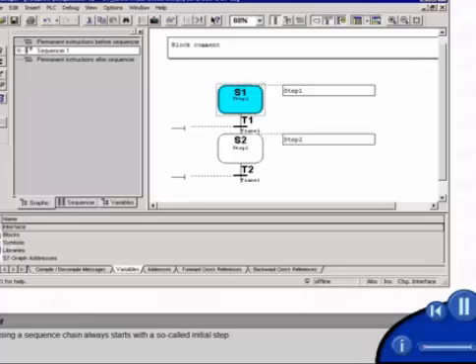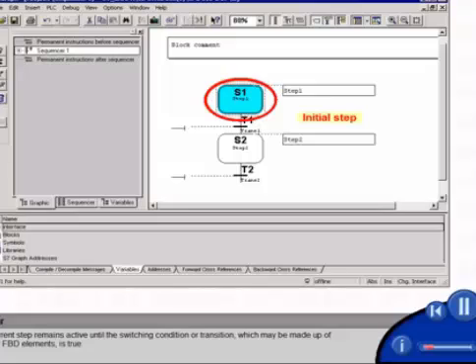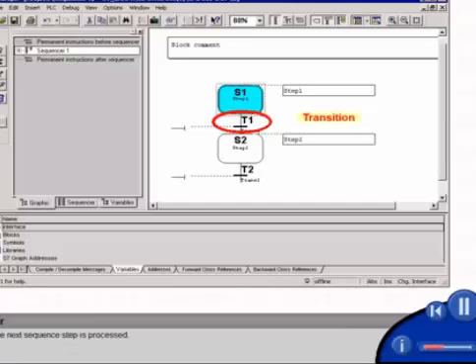Processing a sequence chain always starts with a so-called initial step. The current step remains active until the switching condition or transition, which may be made up of ladder or FBD elements, is true. Then the next sequence step is processed.